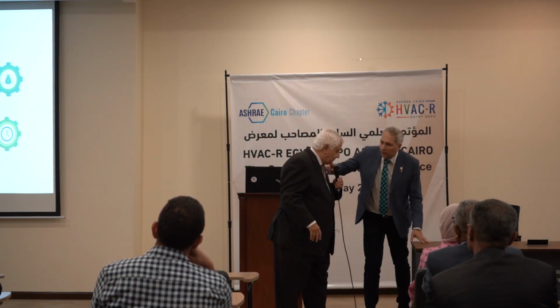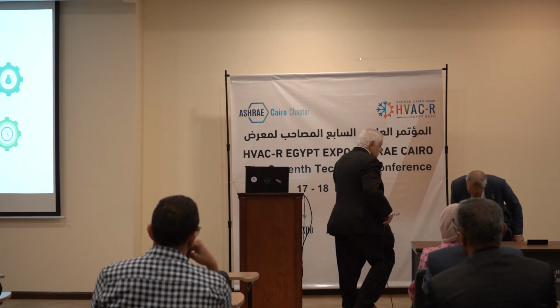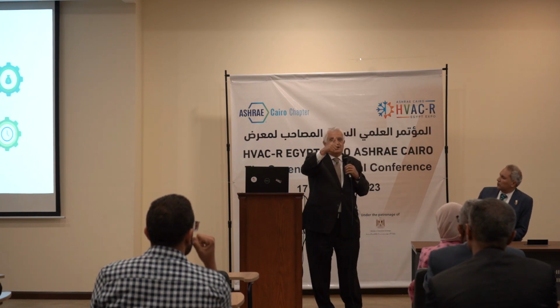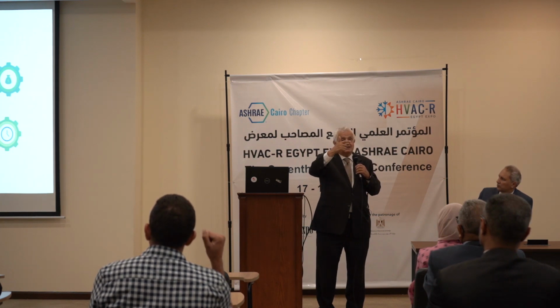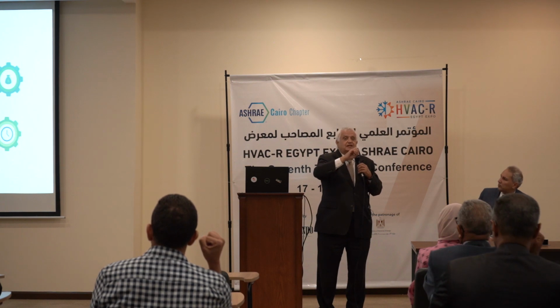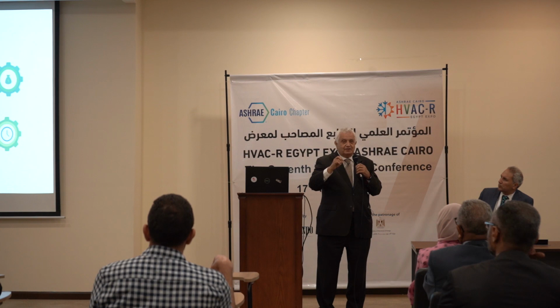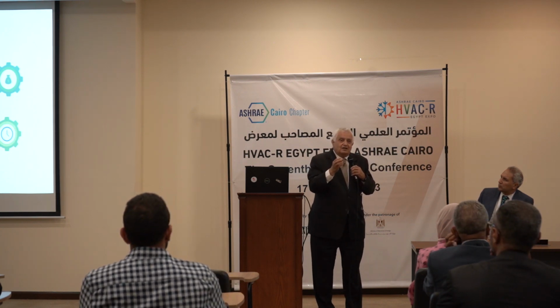And then after that, we added a new dimension to the test. We asked Mr. Hussam Heba, who's now the Minister of the GAFI, which is the Authority of Investment, to do the testing protocol or a formula for seeing which of the 2 systems is better than the other from a financial point of view. So they made a program during the lifetimes of the 2 units, that is around 15 years, and they found out using the capital cost of the machine and the operating cost of the machine, of the DX machine and the IEC-H, which is an evaporative cooling machine, hybrid, and I'll tell you why hybrid very shortly, which of the 2 has a lower net present value.